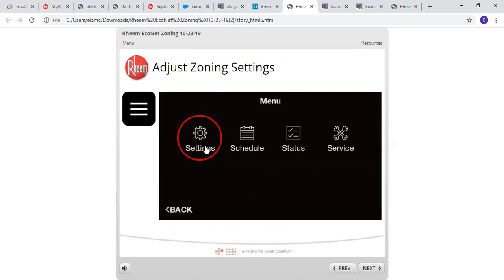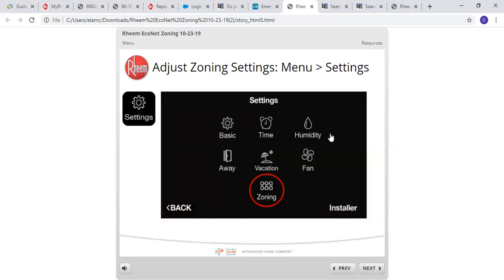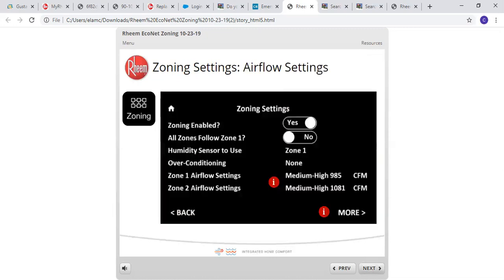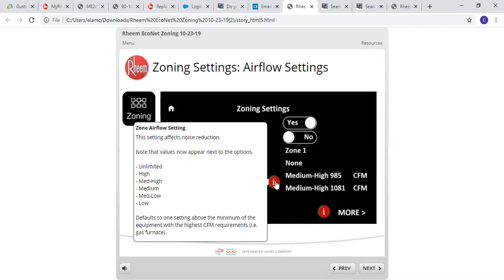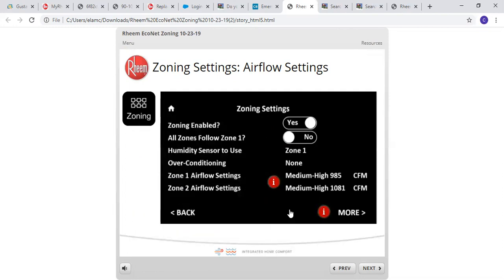Adjust the zoning settings. We have our settings button here. Go to the zoning. And here we can dial these in a little more. So we have our unlimited, high, medium high, medium, medium low, and low. In this case, zone 1 was set for medium high at 985 CFM, and zone 2 was set at medium high at 1081.